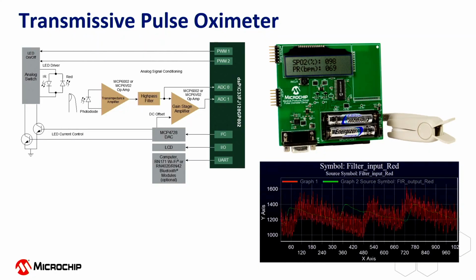Yes. So it looks like first up is the pulse oximeter. Yeah, right. And what the pulse oximeter does, many people are familiar with it. If you've been in a hospital or seen somebody in a hospital, they've got a little finger clip on. That finger clip goes back to a patient monitoring system, and inside the patient monitoring system is a pulse oximeter, which measures your simple heart rate, how many beats per minute, as well as your blood oxygen level. Call it SpO2 or blood oxygen levels.